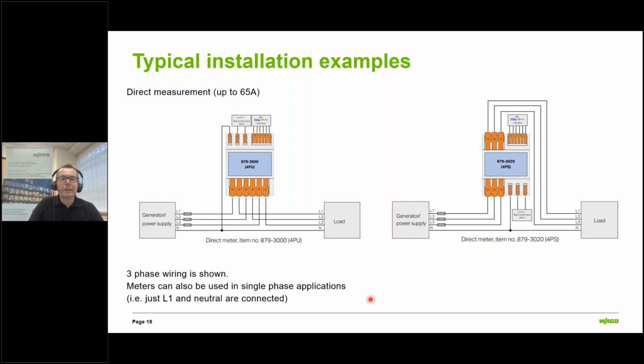So a typical example of how these are installed. This is showing a three-phase implementation, but they can equally be used on single phase just by connecting line one and neutral. And you see that you have the source of power, the three phases feeding into the meter, and conversely back out again to the load. So directly measuring the power up to 65 amps. The difference with this slightly different version of the meter is that the wiring is in this series approach versus a sort of parallel approach. So it's simply to lend itself to different installations and convenience of installation. You can also see that we've got connections for communications and also to choose to toggle through two different tariffs here.